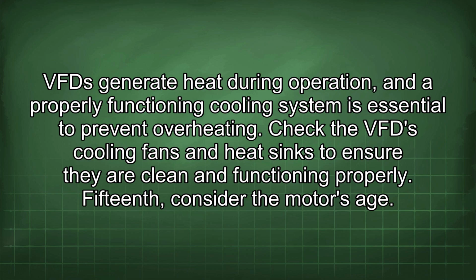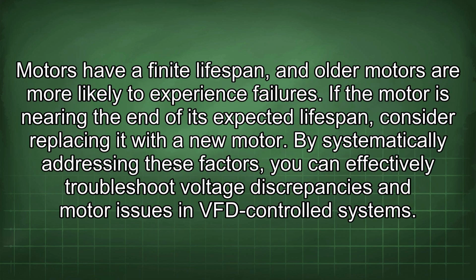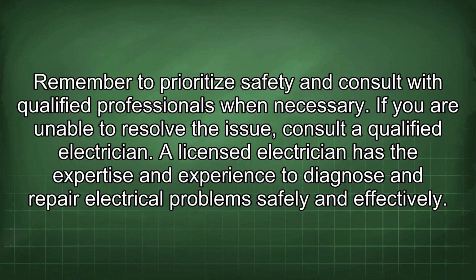15th, consider the motor's age. Motors have a finite lifespan, and older motors are more likely to experience failures. If the motor is nearing the end of its expected lifespan, consider replacing it with a new motor. By systematically addressing these factors, you can effectively troubleshoot voltage discrepancies and motor issues in VFD-controlled systems. Remember to prioritize safety and consult with qualified professionals when necessary.